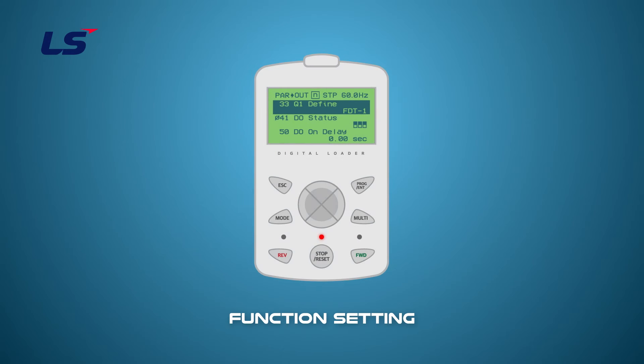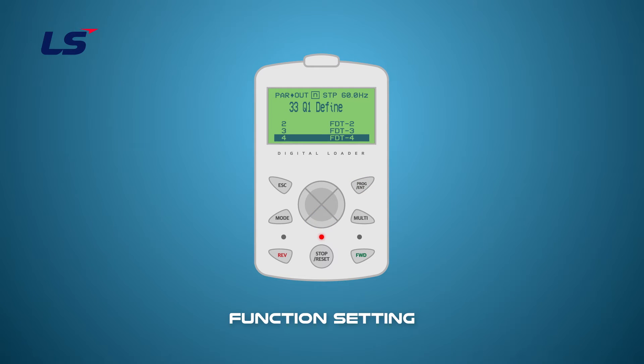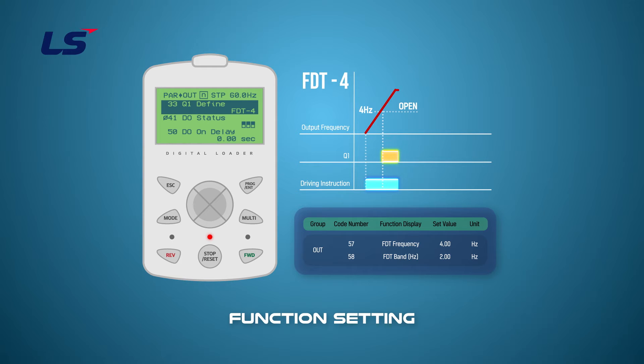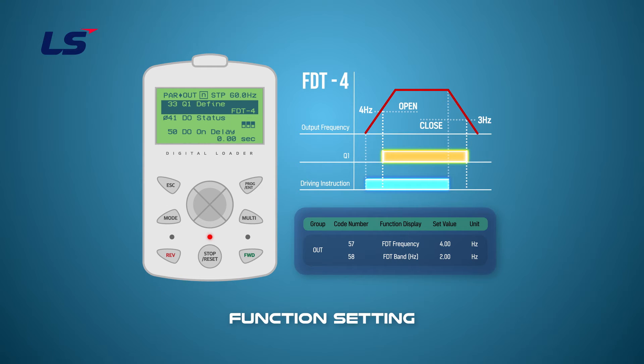We use an output signal, so set FDT4 at OUT group 33 Q1 define. In the operation sequence of FDT4, when the operation command is on, the output frequency increases. When the output frequency reaches 4 Hz, output signal Q1 turns on. After the operation command is off, the Q1 output is off at 3 Hz. These mean that the brake is opened when Q1 is on and closed when off.